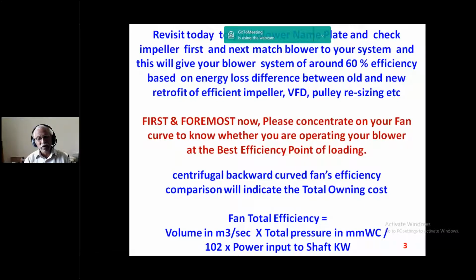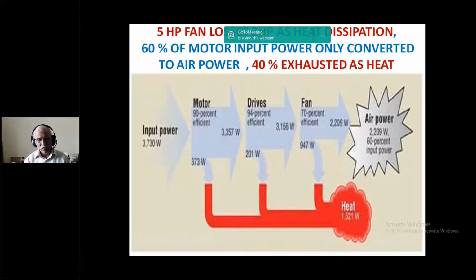We will go in depth into where this can be improved: the energy efficient impeller, and all the retrofits like a VFD or resizing of pulleys and belts, and what all can be done on the existing blower to improve the efficiency. For a typical 5 HP blower, you can see the Sankey diagram for the given blower. The Sankey diagram is the energy flow diagram. Input is almost 3.7 kilowatt, that is 5 HP. Motor is around 90%, drive is around 94%, and the fan is around 70%. Ultimately 1.5 kilowatt, almost 2 HP, almost 40% is lost in the form of heat only.